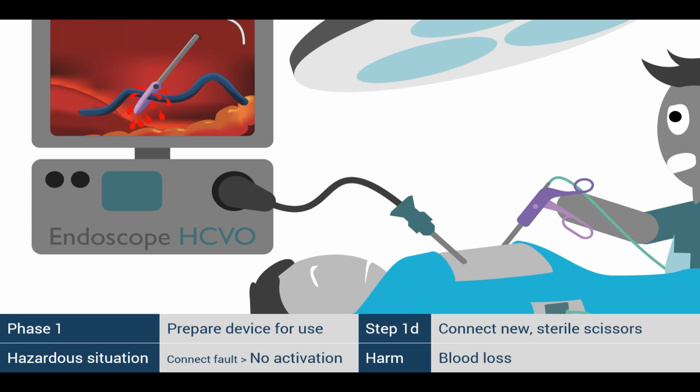If the pins fail due to wrong insertion, it's a random fault. But if they fail due to a bad design or production, it's a systemic fault. There is a probability for each of those, and they share the same potential consequential harms.